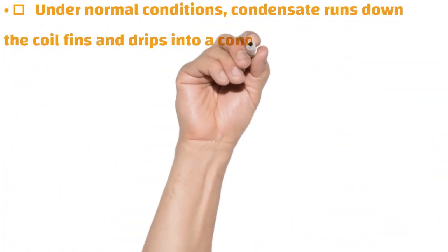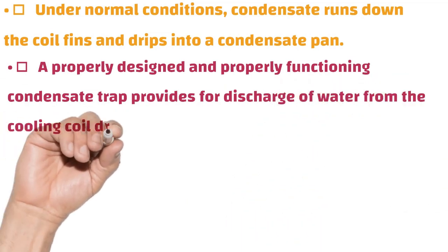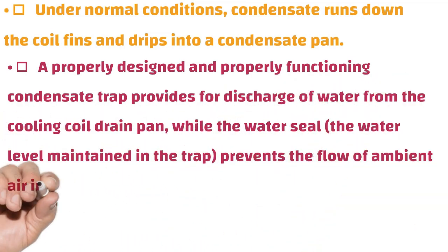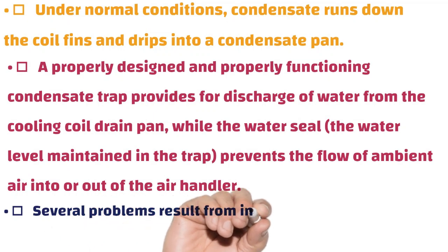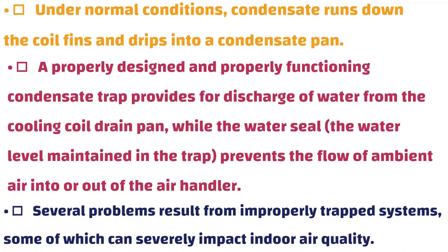Under normal conditions, condensate runs down the coil fins and drips into a condensate pan. A properly designed and functioning condensate trap provides for discharge of water from the cooling coil drain pan, while the water seal prevents the flow of ambient air into or out of the air handler. Several problems result from improperly trapped systems, some of which can severely impact indoor air quality.